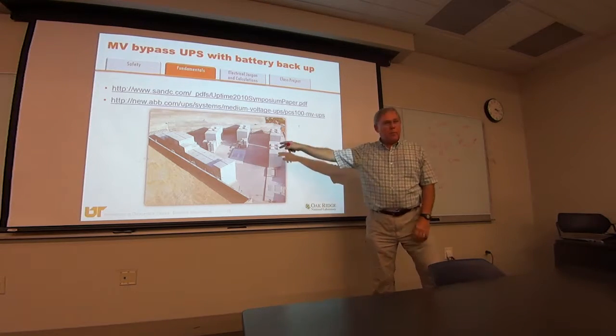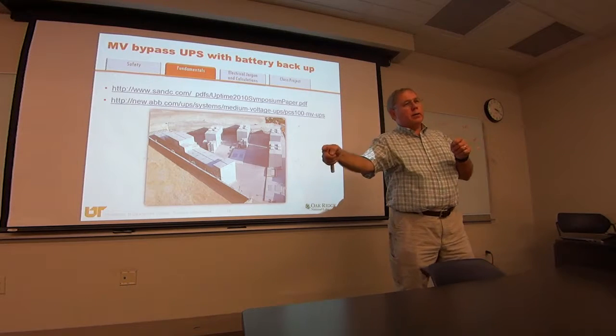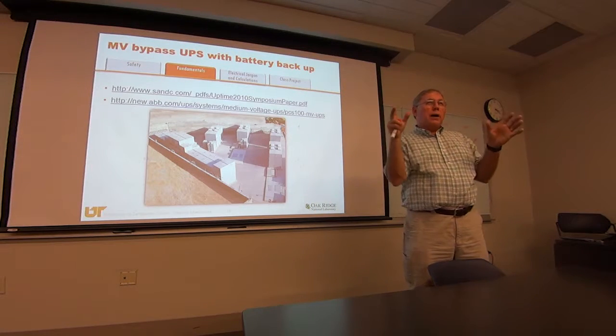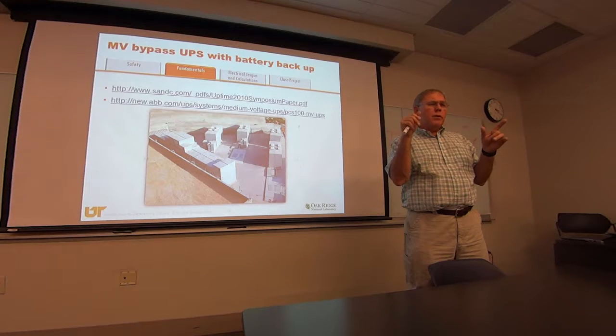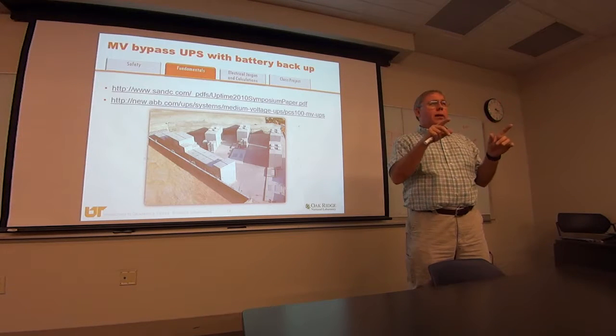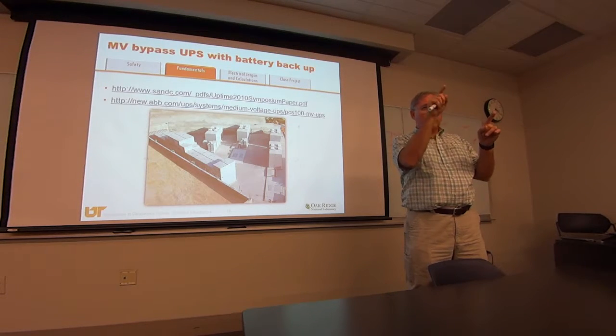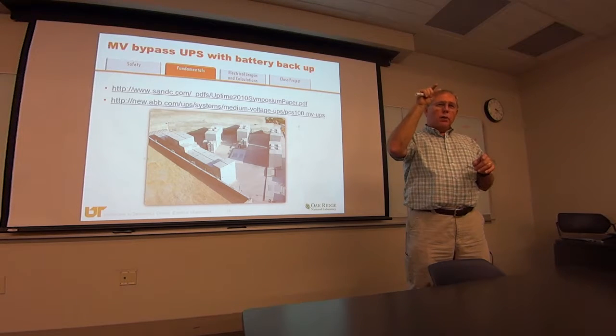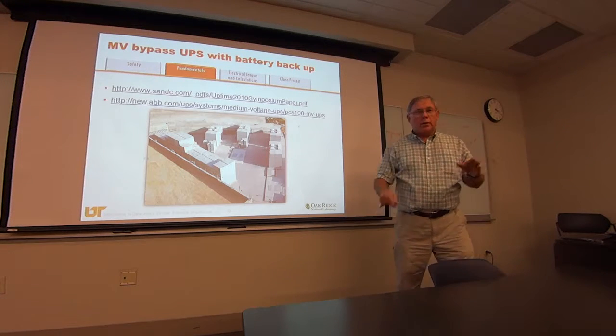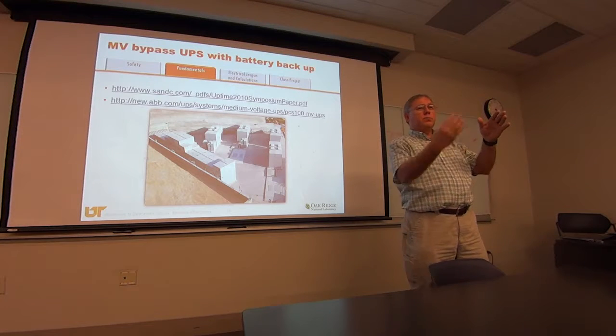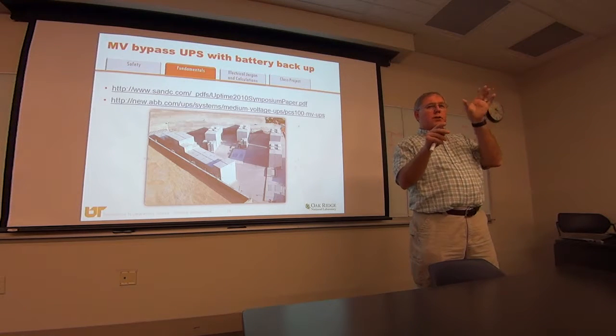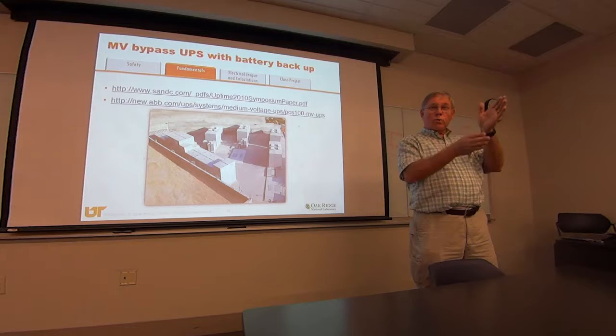Now, this one's a standby UPS. It's in static bypass all the time, and it's watching the power line. Every 20 times a cycle, it samples the AC waveform. And if it sees a 10% RMS voltage drop, it basically cuts the UPS on, and the UPS starts feeding the load, and the static transfer switch cuts off in about a quarter of a cycle.